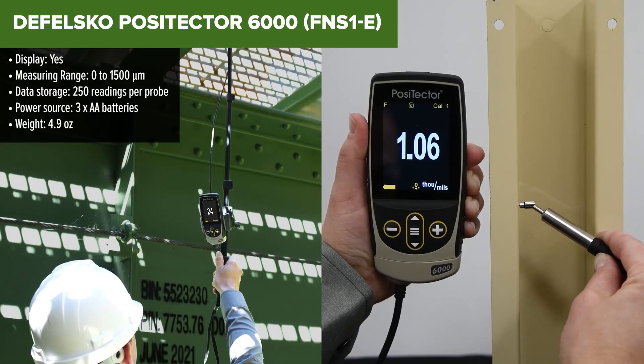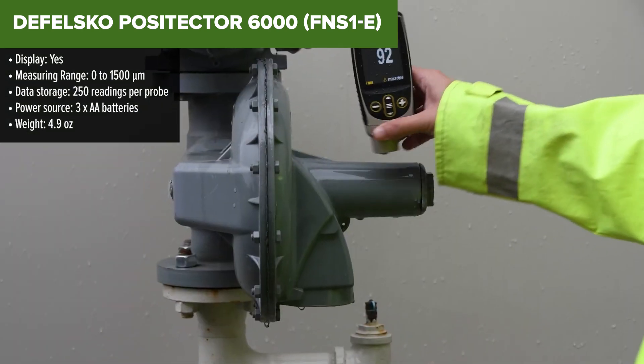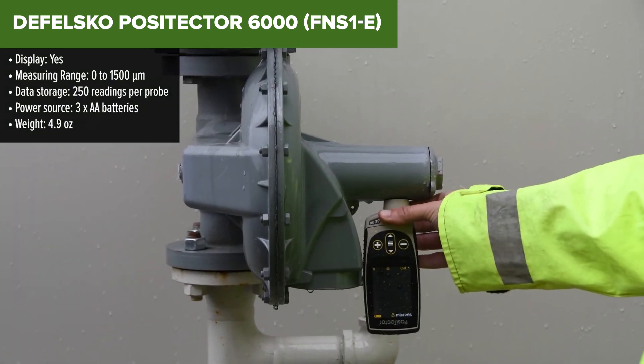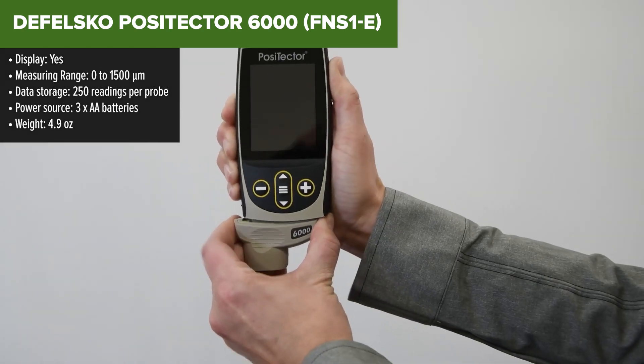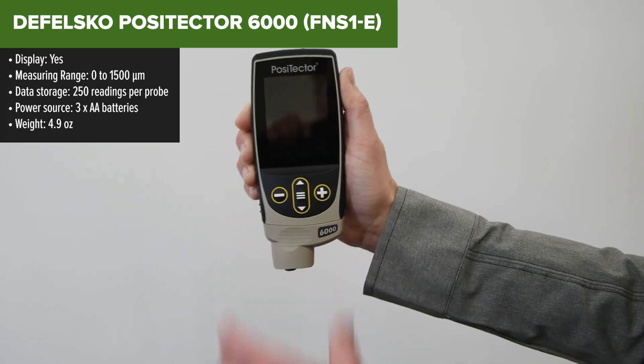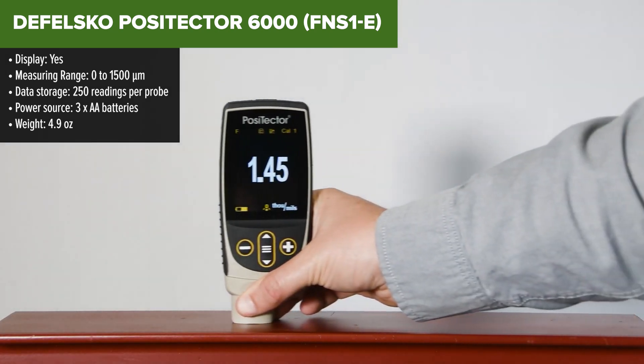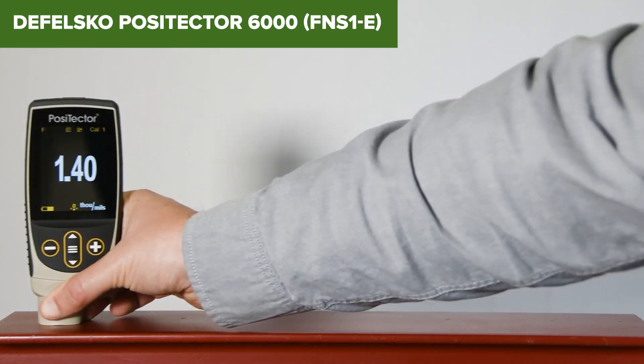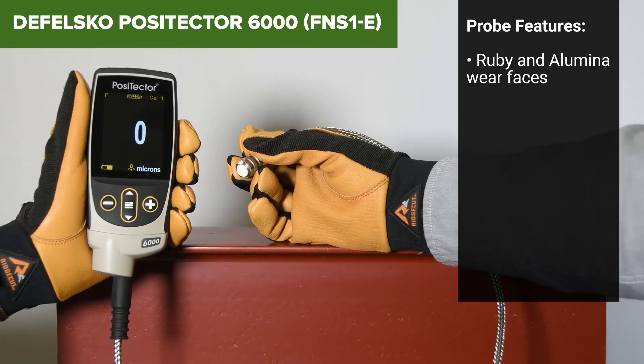The DeFelsko PosiTector 6000 is a high-precision coating thickness gauge designed for measuring the thickness of coatings on both ferrous and non-ferrous metals using magnetic induction and eddy current principles. This model features a rugged, weatherproof design that is resistant to solvents, acids, oil, water, and dust. It includes a durable ruby probe tip and a high-contrast backlit display, making it suitable for use in various lighting conditions.